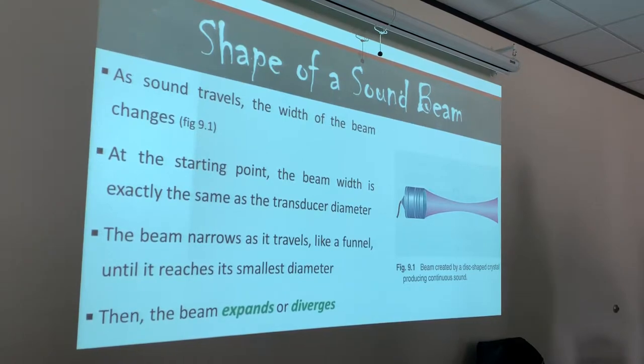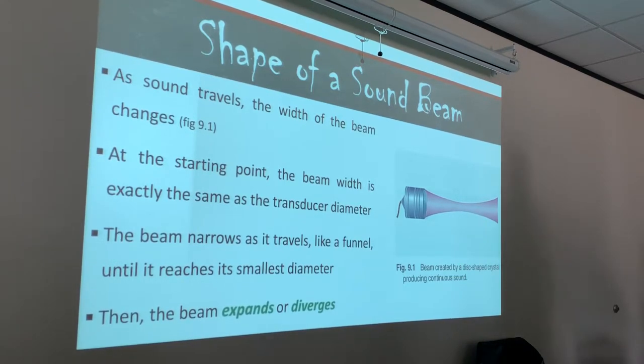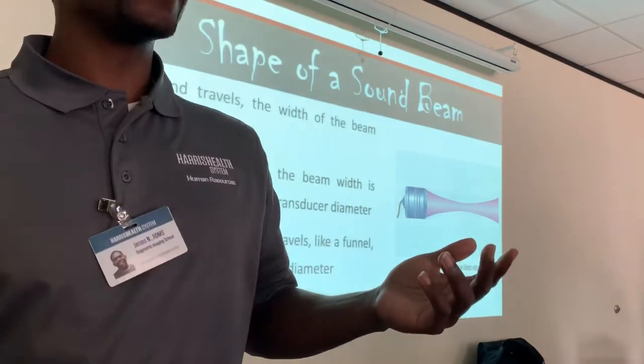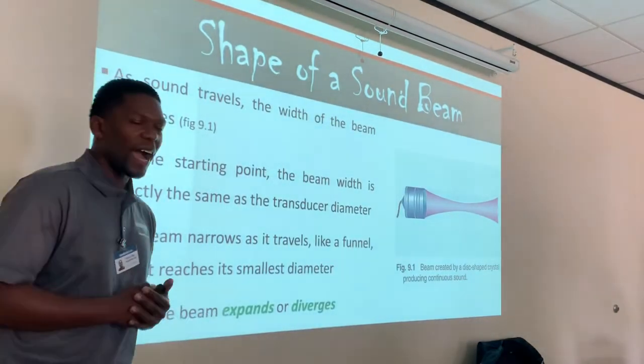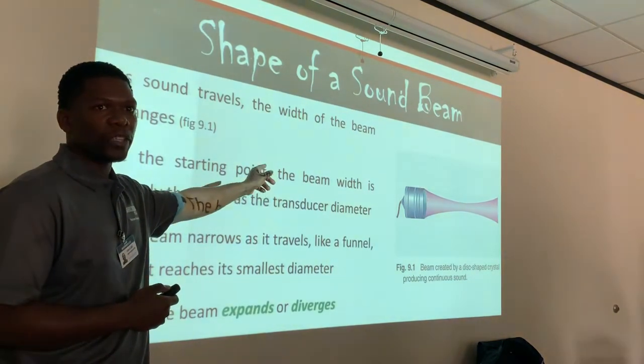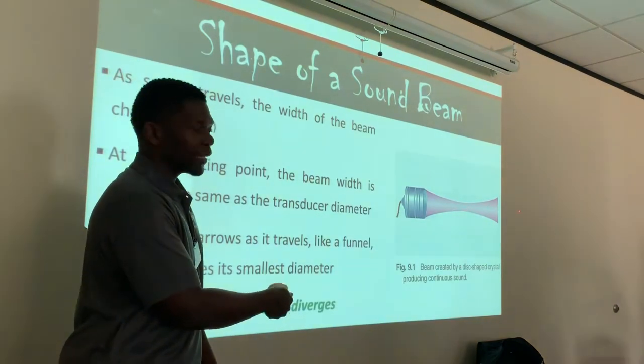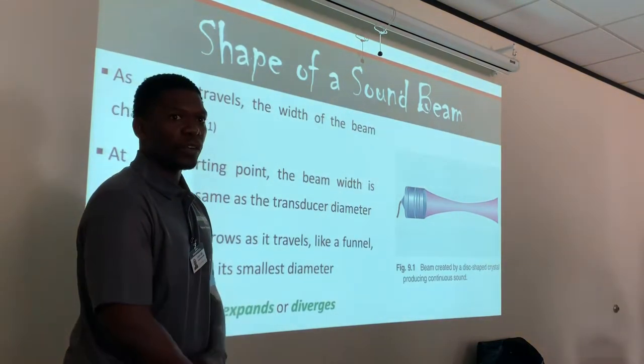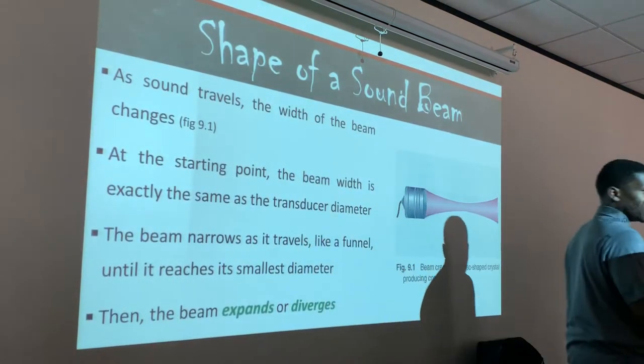In this profile view, we're talking about the width of the beam. Remember, the width of the beam has everything to do with determining our lateral resolution. What determines our axial resolution? Spatial pulse length determines our axial resolution. Our lateral resolution is determined by the width of the beam. So just looking at the shape of this beam, our lateral resolution is going to change over the distance traveled, because our beam changes shape over distance.